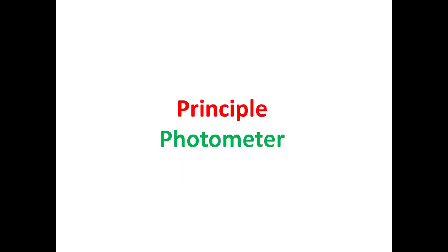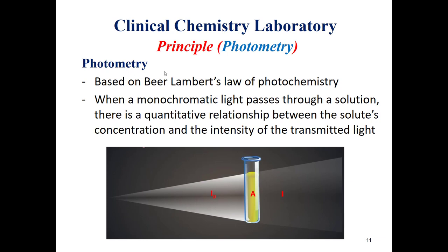Now we'll talk about the principle of the photometer. The photometer is based on Beer-Lambert law. We have two types of systems for photometers: monochromatic and bichromatic. Monochromatic uses only one specific wavelength for the measurement of an analyte, whereas the bichromatic system uses two wavelengths, which is usually used by Roche Diagnostics. One wavelength is used for the measurement of the analyte or chromogen, and the second wavelength is for the measurement and elimination of light interference.